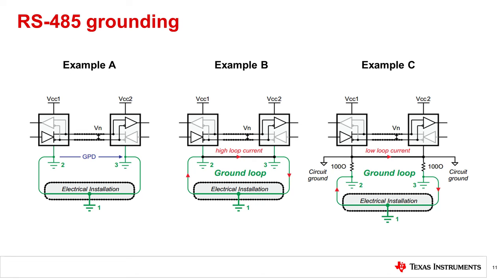There are a few different ways grounding can be accomplished in an RS-485 system. In example A, the system is vulnerable to high ground potential differences; if the ground potential difference exceeds the limit of the device, it could stop working or even be damaged. In example B, if a high ground potential difference is present, large ground loop currents could form which can be coupled into the data lines as common mode noise. Example C is recommended by the RS-485 standard: adding series resistors lowers the loop current, but noise could still exist.